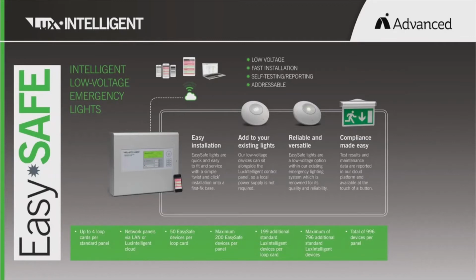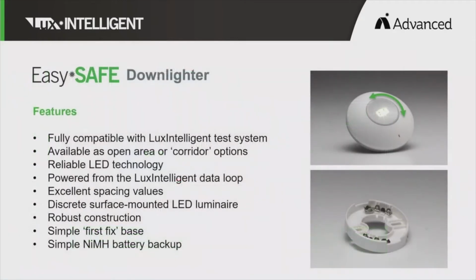of the two systems. Firstly, we have two downlighter luminaires. The first is a bright open area luminaire, and the second is a asymmetric or corridor lens version, which is perfect for reducing the number of devices needed in narrower escape routes. We can provide the spacing data from their datasheets as well as downloadable photometric files, IES or Lumidat, and that goes for all of the lights available from Advanced. Both devices, when ordered, come with their own battery backup, which sits in the back of the device and plugs in via a simple press-fit connector.